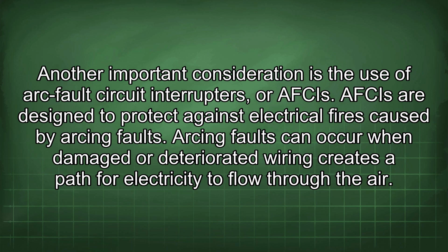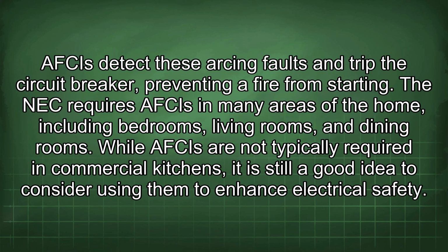Another important consideration is the use of arc fault circuit interrupters, or AFCIs. AFCIs are designed to protect against electrical fires caused by arcing faults. Arcing faults can occur when damaged or deteriorated wiring creates a path for electricity to flow through the air. AFCIs detect these arcing faults and trip the circuit breaker, preventing a fire from starting. The NEC requires AFCIs in many areas of the home, including bedrooms, living rooms, and dining rooms.